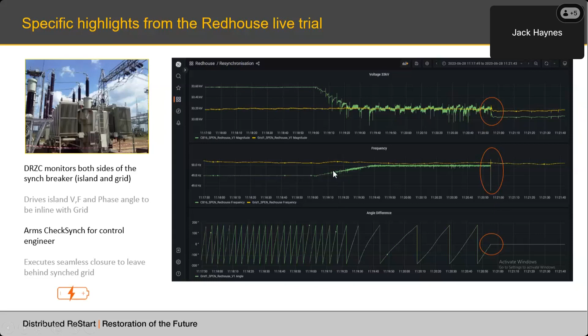And then the last highlight I wanted to draw your attention to was when we were energizing the transformers. One of the phenomena that causes issues when back energizing the network, like we were doing in this case, is the inrush current of the transformers. The inrush current causes a reactive power draw and pulls the voltage down. So we had installed a device called a point on wave relay, which works by measuring the point on the wave of when the transformer that you're looking to energize is de-energized. So it memorizes that point, which is driven by the remnant flux in the transformer.